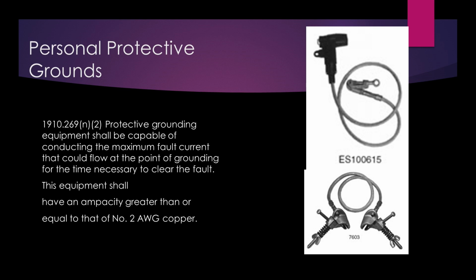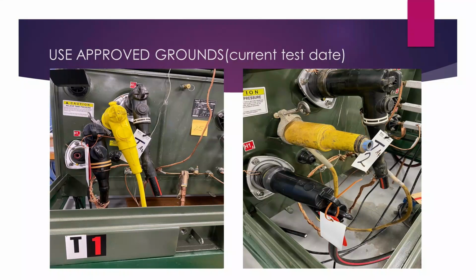Those engineers do something called an arc fault analysis. They go out there and look at the impedance of the power transformers, the size of the wire, the distance, and all that, and they formulate and calculate to give you the available fault current at spots in your system. What they do is take that information and size your FR clothing to it as far as calorie rating, and they also use that to size your grounds and stuff. So 2-0, 4-0, whatever you need, they're going to size it to that. But just know it cannot be any smaller than a number 2.